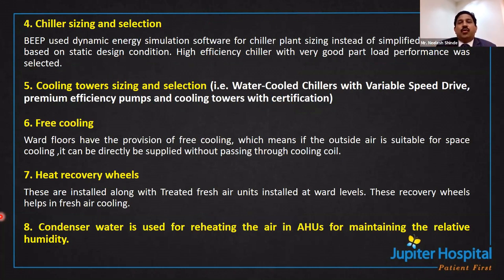It always depends on time. In the morning, the load will be maybe around 600 TR, as an example. At night it will come down to somewhere around 250 TR. So there is a huge difference. For 12 hours there is a different load, and for 12 hours there is full load. So we should have a chiller with good part load performance. That is very important.